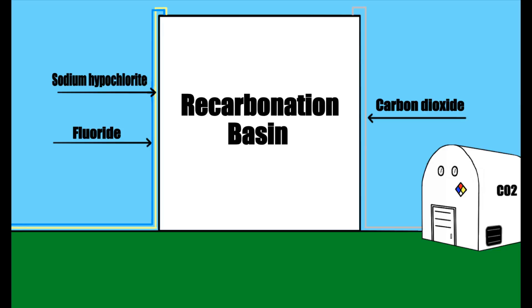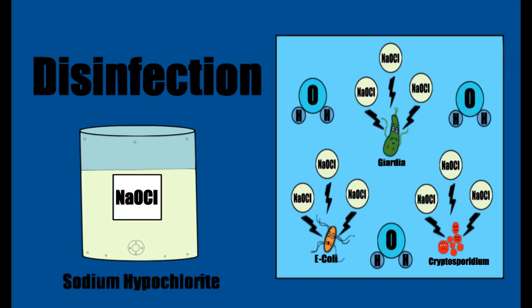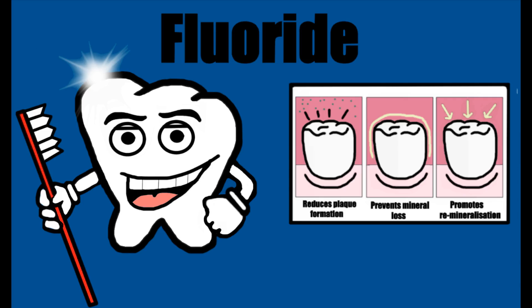After the water has been softened, it travels to the recarbonation basin. Carbon dioxide is added to stabilize the water and lower the pH. Sodium hypochlorite, or bleach, is then added to kill off any potentially harmful bacteria, and a small amount of fluoride is also added to help reduce tooth decay.